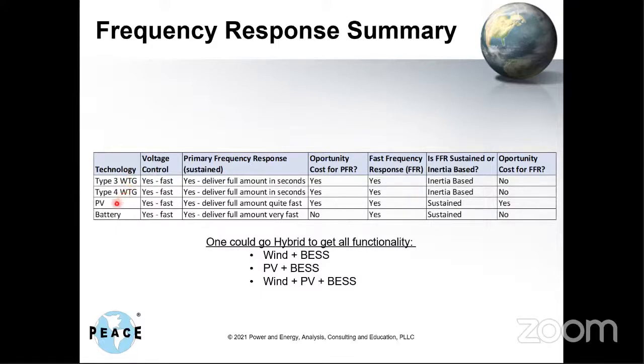If you want to do primary frequency response on, for example, a wind plant or a PV plant, you have to keep some of the incident wind or solar energy in reserve, meaning you're not generating the maximum available energy. You're losing some money - say if there's 100 megawatts worth of wind energy hitting your plant and you're only generating 90 to keep 10 in reserve, that 10 is a lost opportunity cost because it won't be there forever. When the wind dies, it'll go away and you've lost the opportunity to sell that power. So there's some opportunity cost in that case.